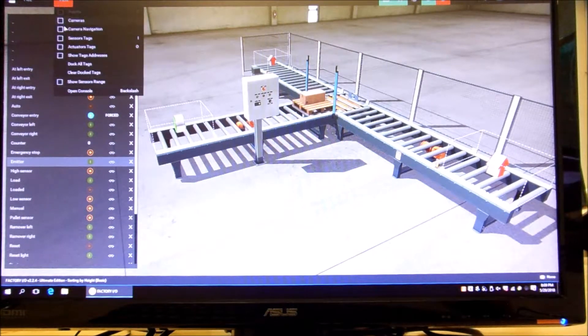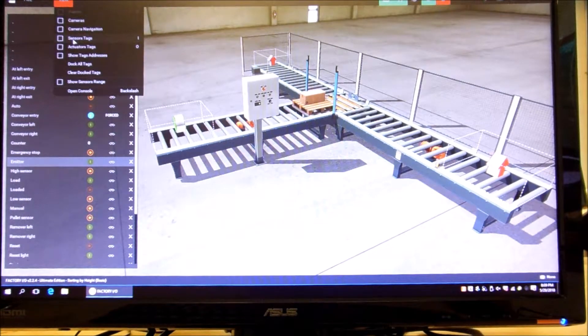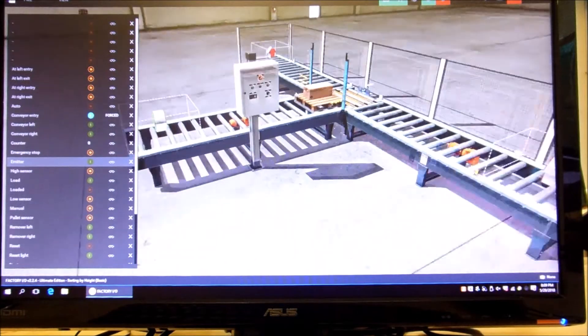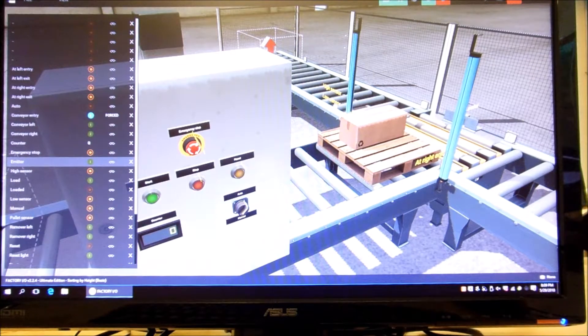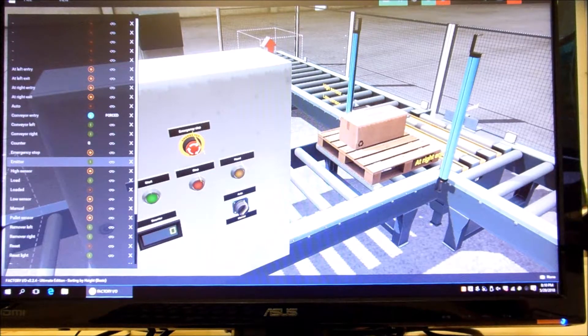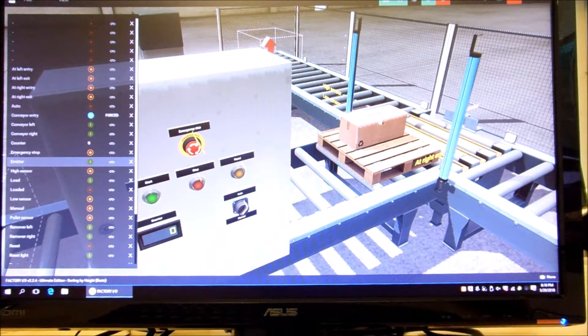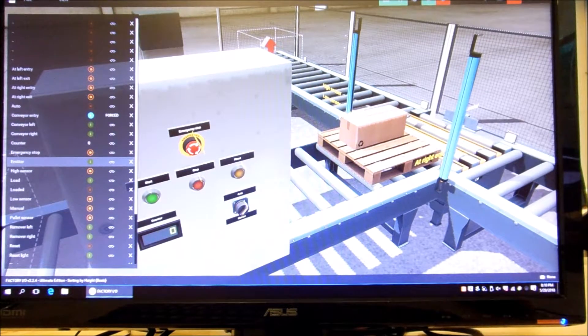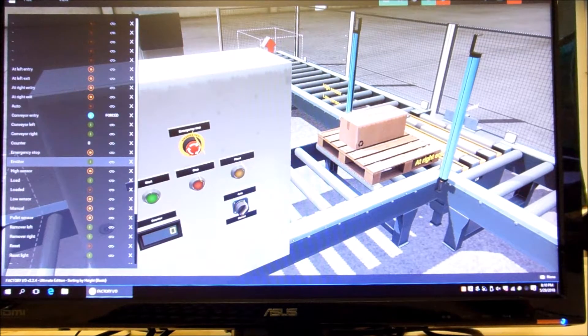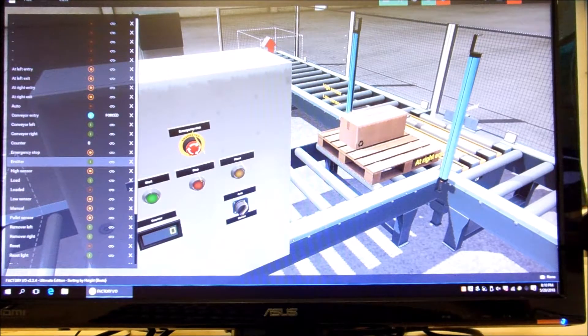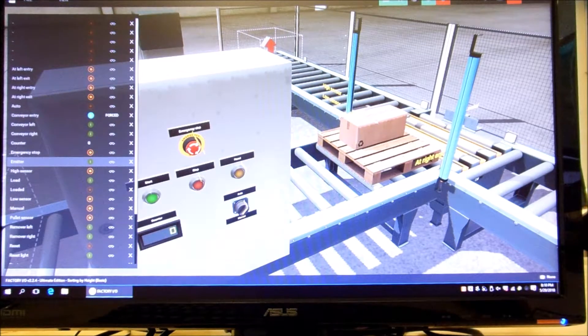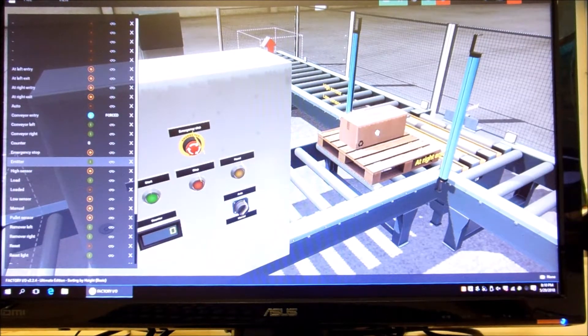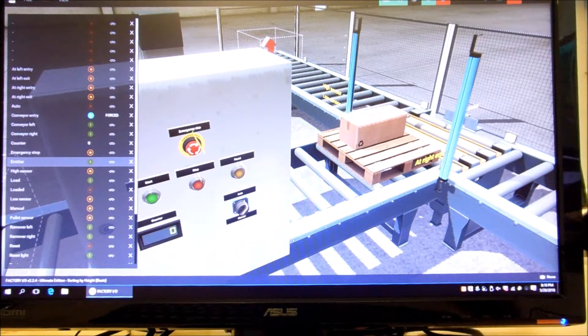And if we look in the view, we can turn on our sensor tags. And this will show us, and I'm going to zoom in here. So this shows us where our sensors are. So the pallet sensor is here, our high sensor and our low sensor are here. And basically these are through beams. So they go from over here and then they're received over here. Now when the pallet comes in, it blocks it at this front edge. So the pallet becomes, it sees the pallet sensor before it sees these, because the box is pushed back from the edge. And so it sees the pallet, and then it sees both the high sensor and low sensor, because this is actually a high box. If it were just a low box, which is a really flat type of box, it would just get the low sensor.